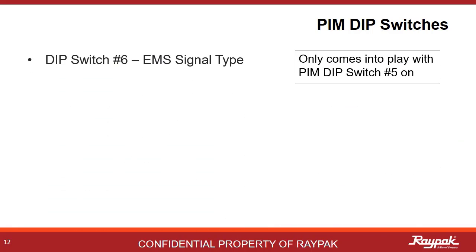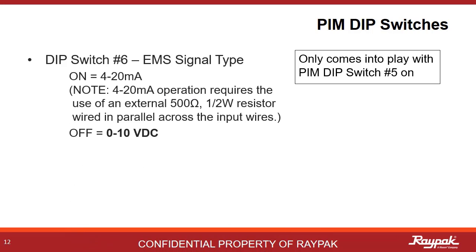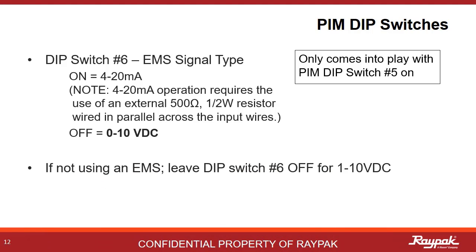Dip switch number six only comes into play when dip switch number five is on. Here is where you select what kind of signal type is needed. On indicates a 4 to 20 milliamp signal, while off indicates a 0 to 10 volt DC signal. If not using an energy management system, leave dip switch number six on the PIM off.